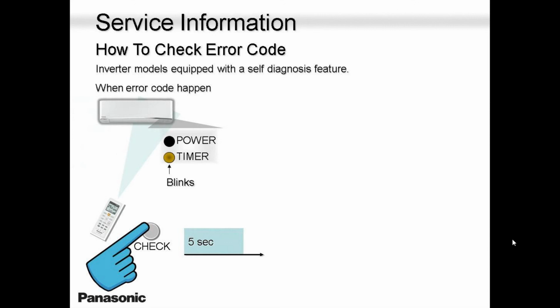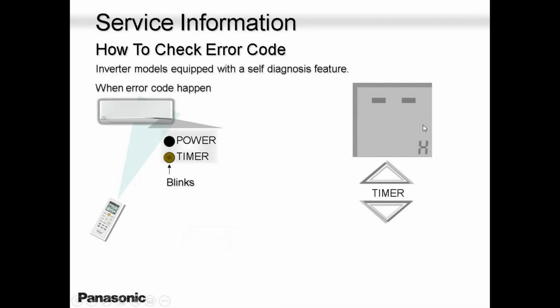It's very simple. When the timer light is blinking, definitely you have an error code. If the timer light is steady, the homeowner, for some reason, put the unit in timer settings. Okay, there's a difference between blinking and steady. And when this power light is blinking, the unit is in defrost cycle or standby mode. So when this power light blinks, there is no error code, guys. Only when this timer blinks, there is an error code. So please remember that. When the power light blinks, you are either in standby mode or defrost cycle. When the timer light blinks, you are in an error code state. Pull the error code, find what the error code is, and fix it.